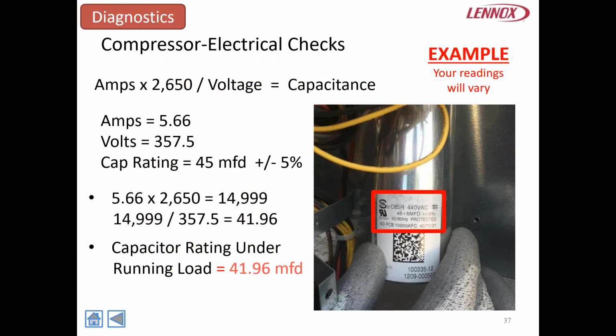Then all you do is just plug in the numbers, right? You take your amps times 2650 and divide by the 357.5 voltage. The cap is rated for 45, and you can test each one of those individually. You can test the Herm side, you can test the fan side. In this example here, we come up to be 41.96. So this is generally where I ask, is this capacitor good or bad? And I get some hands that come up and say, well, capacitor's good. Some are going to say it's bad. But plus or minus 5% in our example here on the screen, this capacitor is actually bad. So that's something that I do quite a bit. Run test, load test. It's going to give you a true reading of what that system's doing.